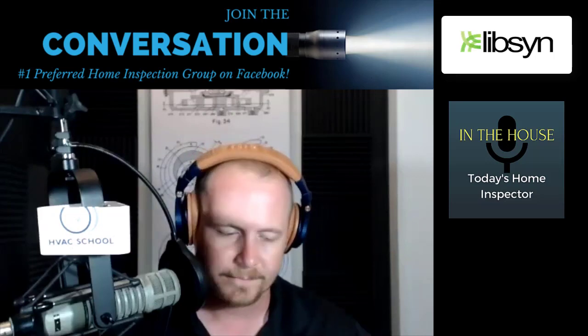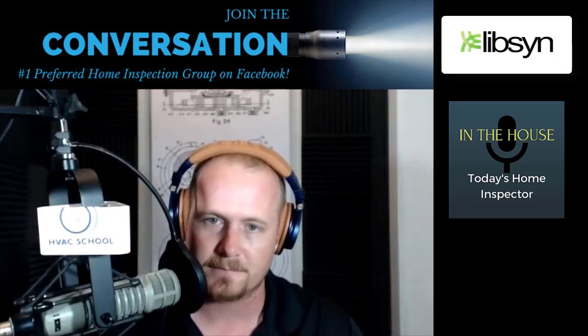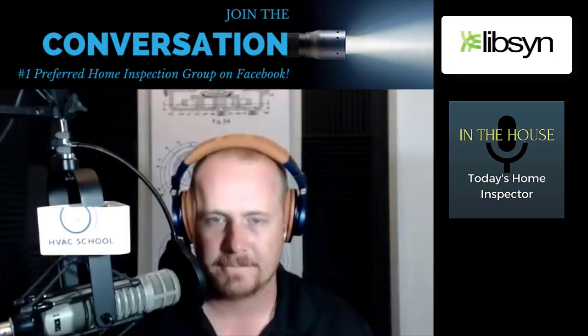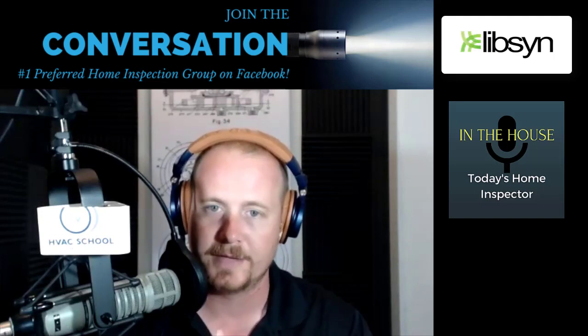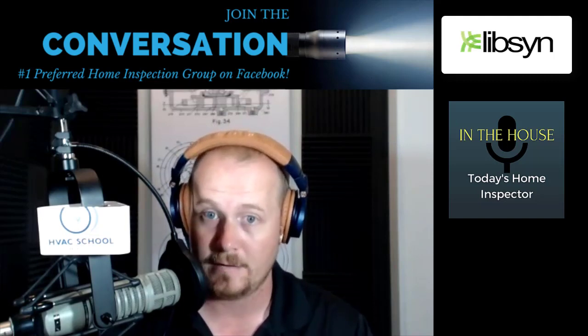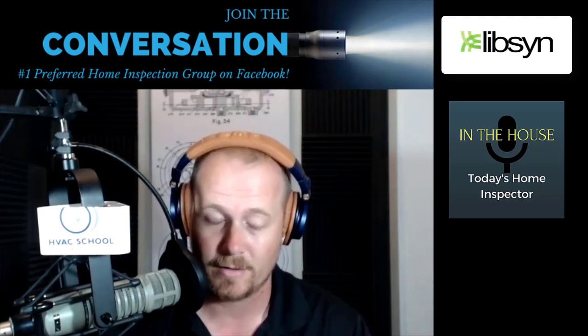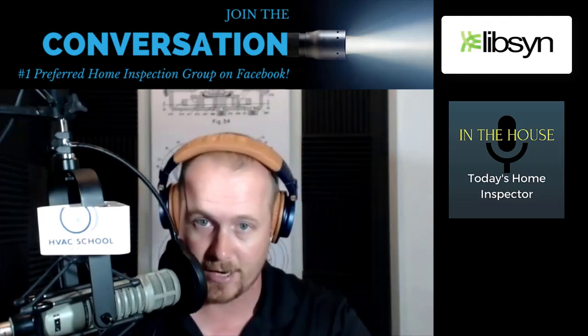That's all, just one. And inside, so that way you kind of know the relative humidity inside the space and temperature. So humidity and temp, dry bulb. Yep. So here's where we're at right now. You've got dry bulb temperature in the supply, dry bulb temperature in the return, humidity in the space, outdoor temperature in the shade. That would be excellent to know as well. So don't get it outside in the air, just in the shade.